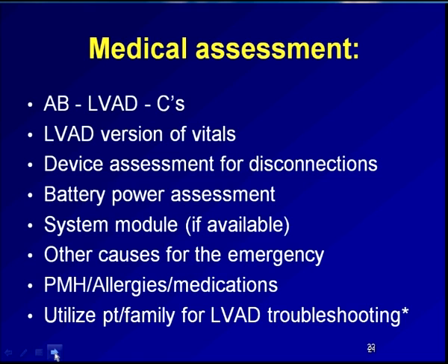Check the device assessment for disconnections. So start from the patient, work your way back to the device, check every point of connection, make sure something didn't become disconnected, which would be a very easy fix. Or start from the device and work your way towards the patient, checking every single thing that could possibly connect or disconnect. Check for battery power.